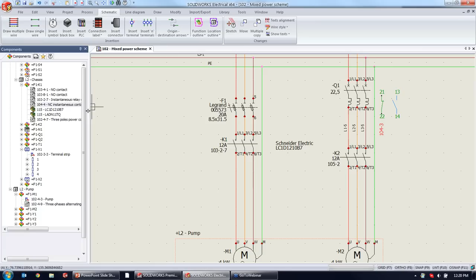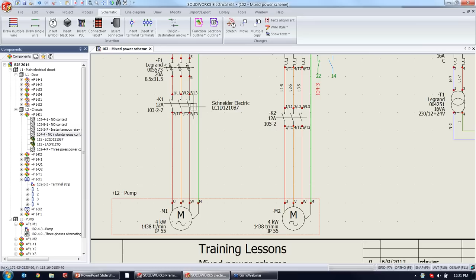So that looks pretty good. The last thing I want to do is tie a terminal block to these 8 wires that I just drew. I'm leaving my control cabinet, or main electrical closet, and tying into a motor. I don't want a direct line to one of these; I want something that can break if I oversurge or overheat.